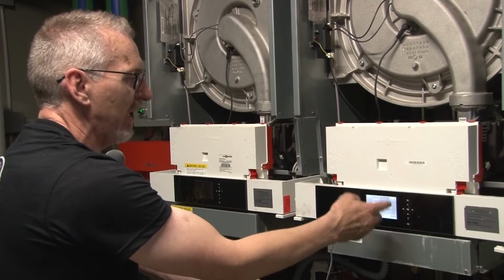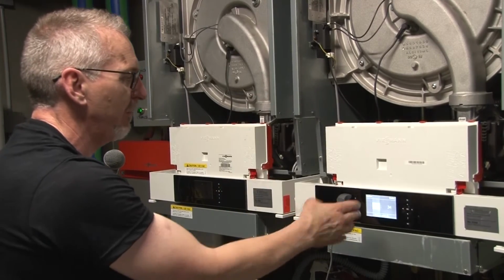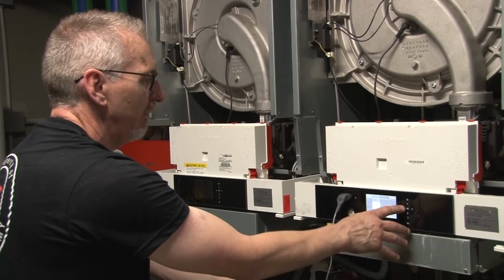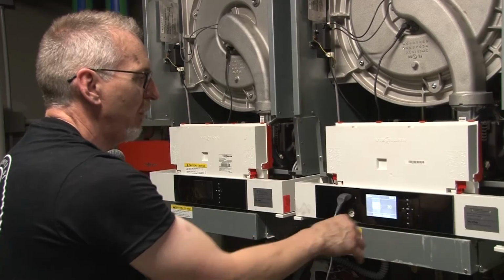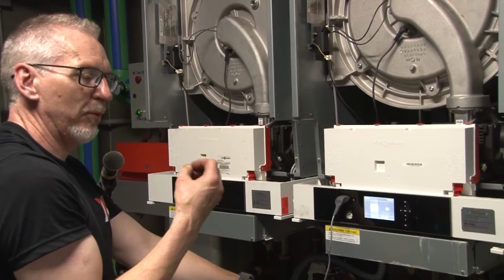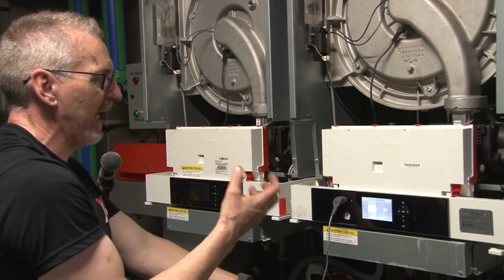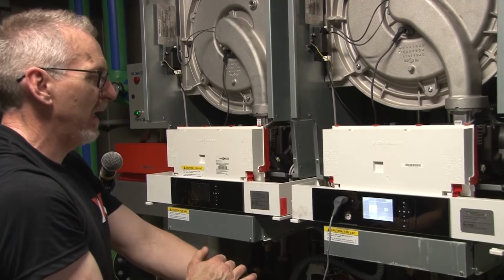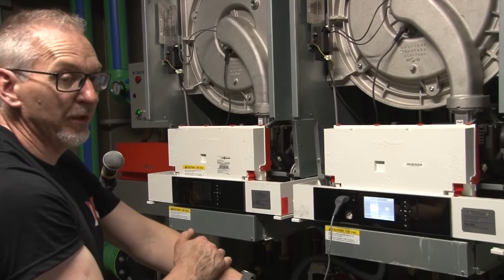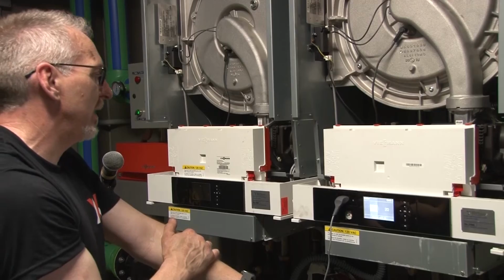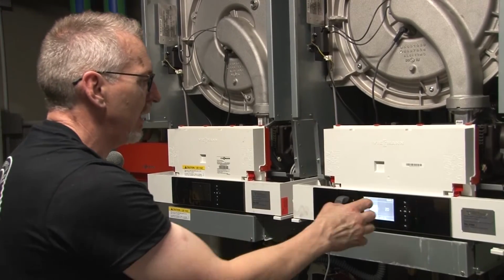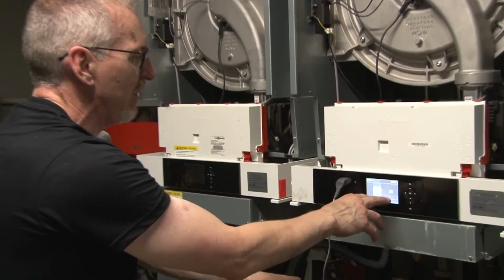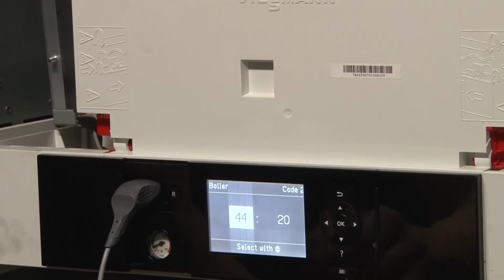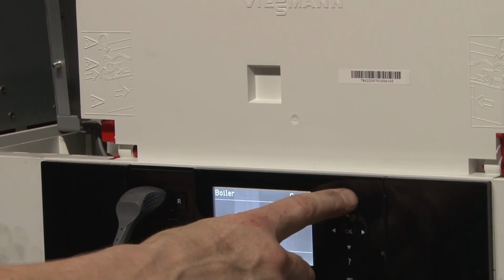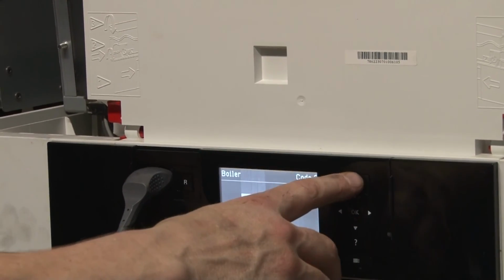46 tells me that I've got 34 more burner on-off cycles before it calibrates again for combustion. And 44 tells me flame recognition, or essentially how quickly the gas valve opened and we had flame formation, so about 2 seconds, which is really a good number. So this boiler looks like it's in good working order. I just wanted to reference these, they are not in the manual. I put them in the supplement that you guys have with you, in case you want to review that. It tells you how to get into all this particular area of the boiler.